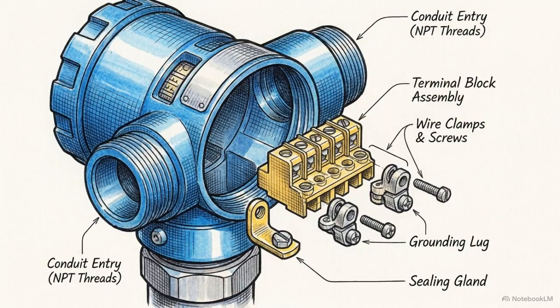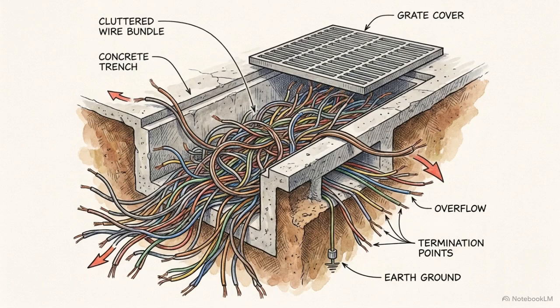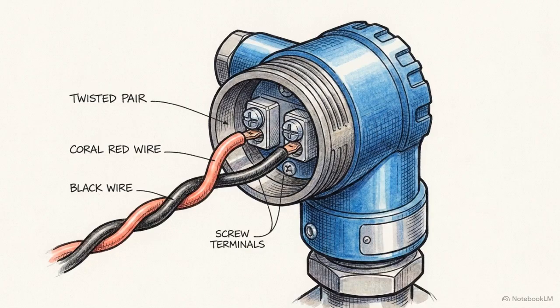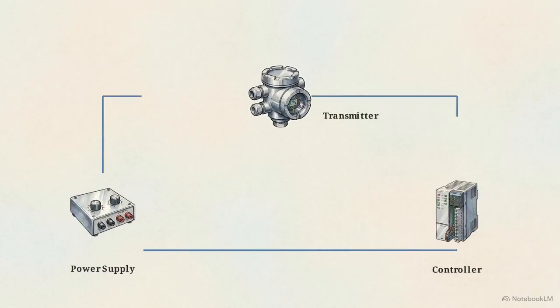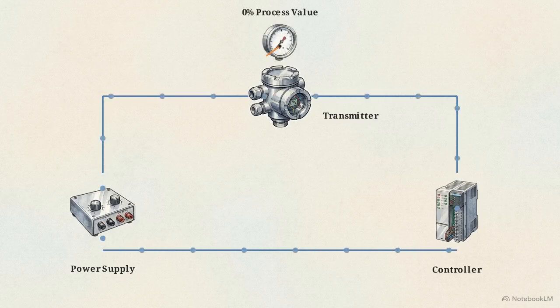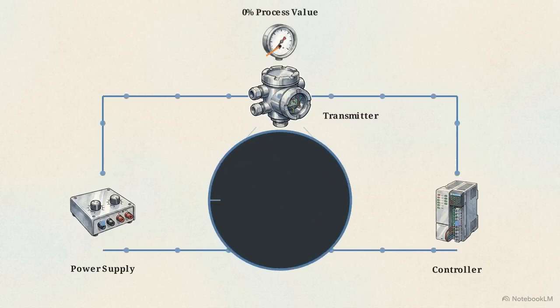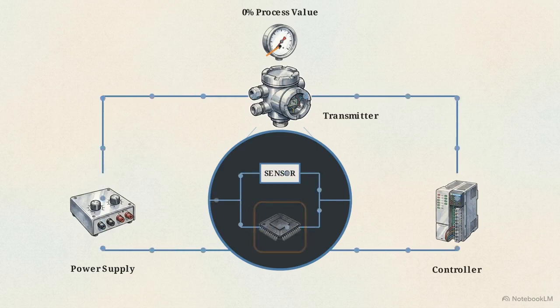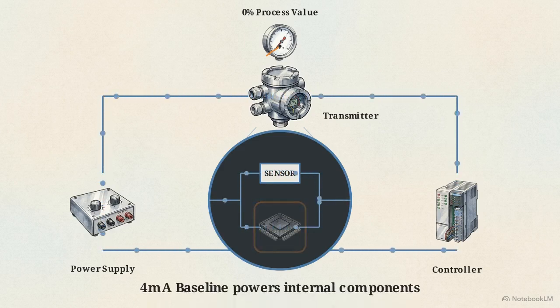This live zero solves a secondary infrastructure problem out in the field regarding device power. Running separate power and data cables to thousands of instruments is expensive. Instead, engineers use two-wire loop-powered transmitters, which use the exact same pair of wires for both signal and power. Here we see how the transmitter utilizes that continuous 4 milliamp baseline. Even when the process measurement is at absolute zero, there is enough current flowing through the loop to run the device's internal microprocessor and sensor arrays.